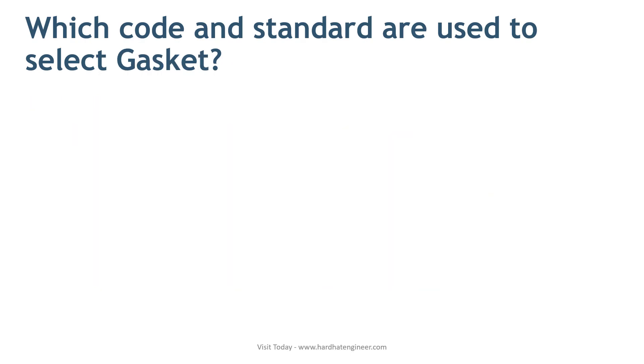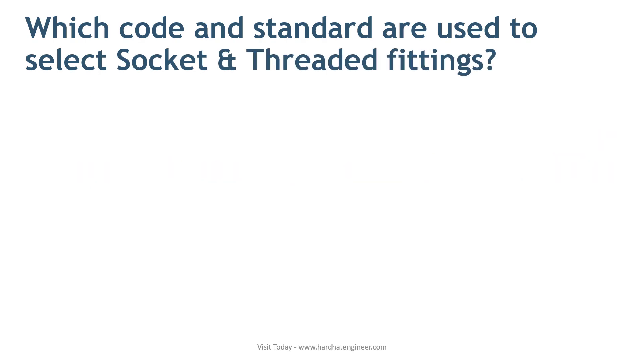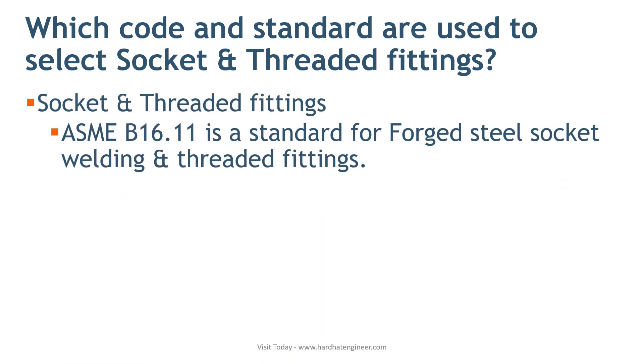Next is gaskets. ASME B16.20 is the standard for metallic gaskets for pipe flanges, and ASME B16.21 is the standard for non-metallic gaskets. For socket and threaded fittings, ASME B16.11 is the standard for forged steel socket welding and threaded fittings.